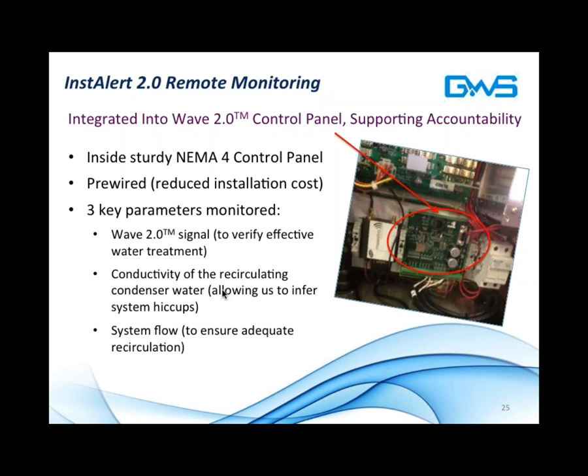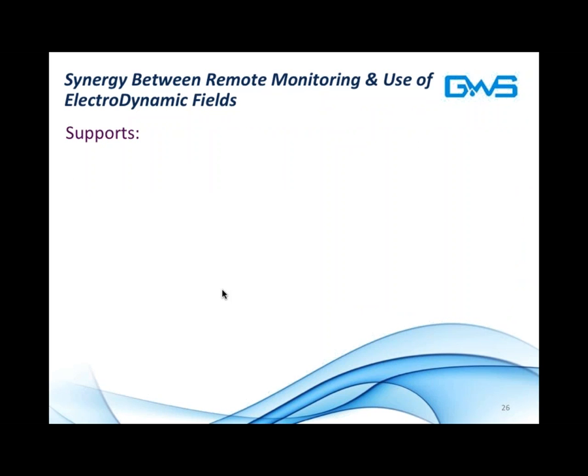The third thing we're monitoring is system flow. And of course, system flow tells us that there's recirculation in the system, something that's also crucial when using chemical inputs. With these three key parameters, we can essentially eliminate 98% of system upsets that have nothing to do with the water treatment specifically. The other key part of this is that this system is scalable to measure water volume inflows and outflows. And this is something we're just pioneering now, and I'm happy to discuss this with you more offline. I'll share some exciting results that we've had here in just a second.